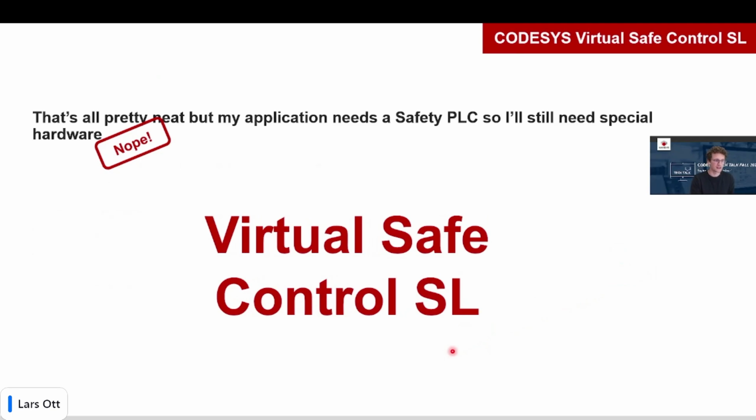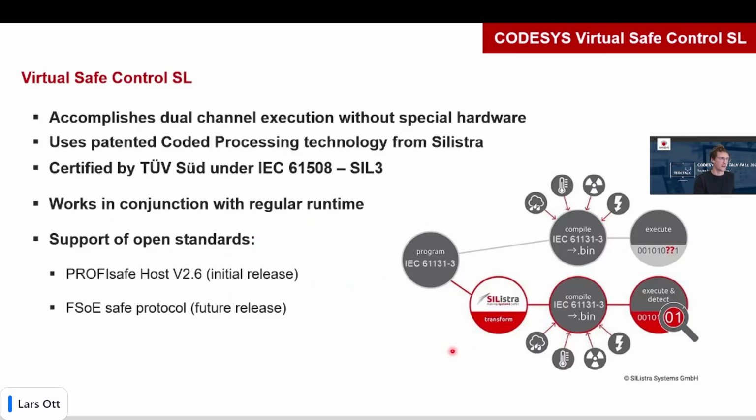We're going to bring it on the market later this year. And it actually does the dual channel execution that you need for SIL3 safety, but without special hardware. It uses a patented coded processing technology from another German company called Silistra. The product we have is already done. It's currently in the process of being certified by TÜV SÜD under IEC 61508 for SIL3.